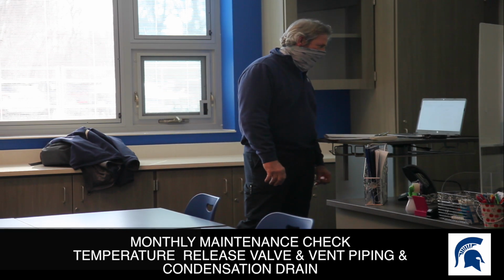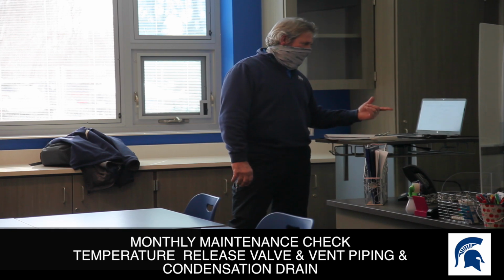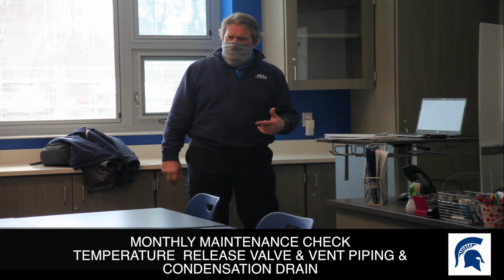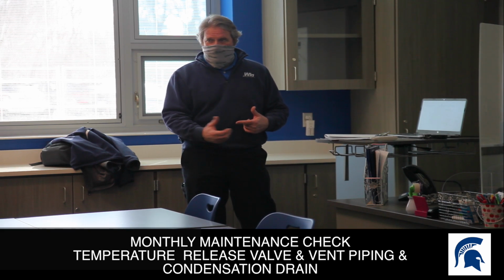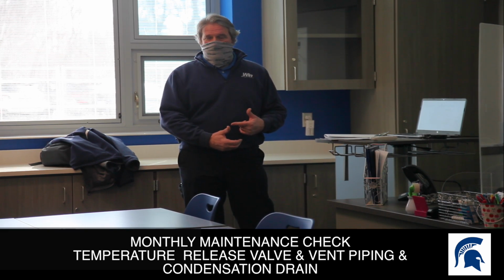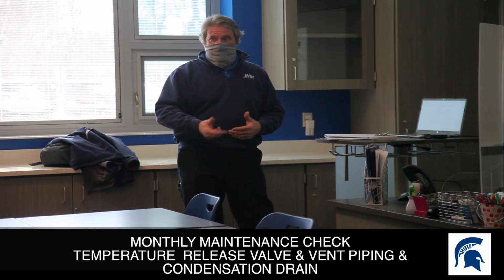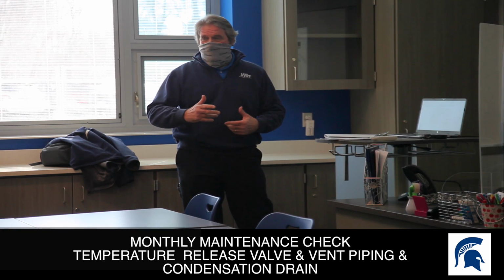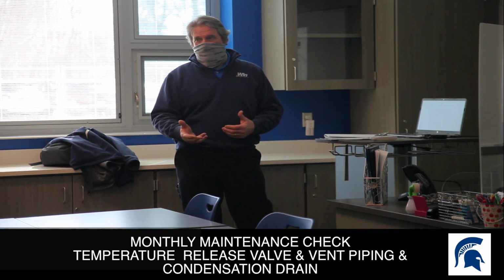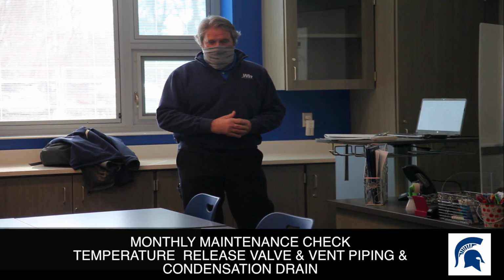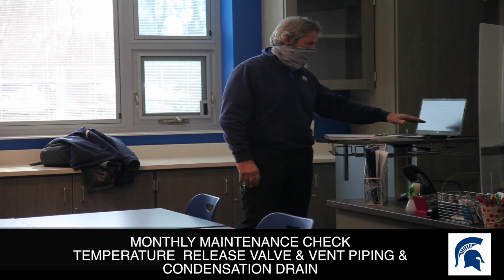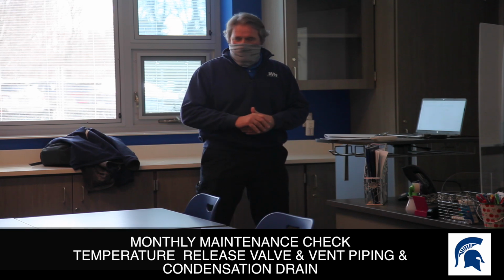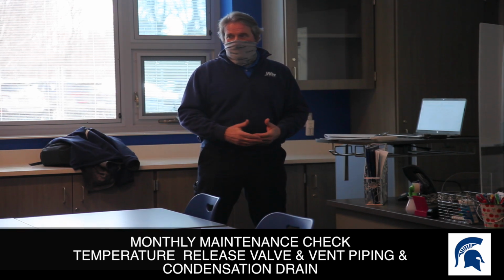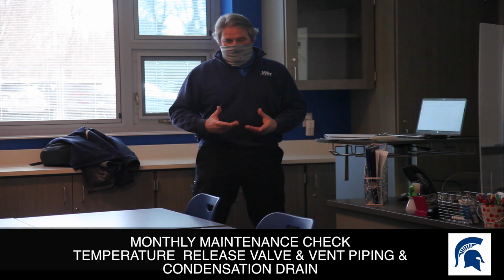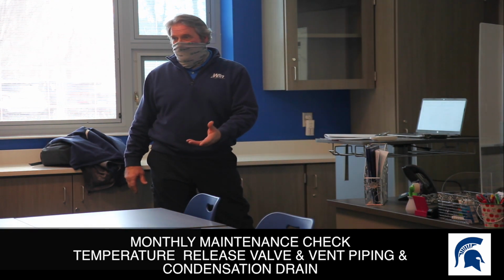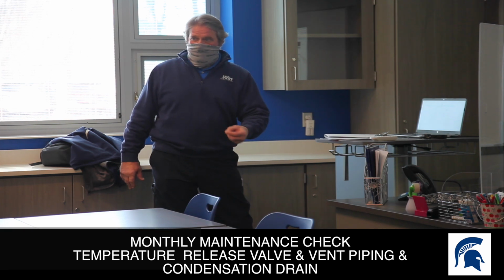And then your condensate drain, you should have the condensate drain there with, I think you have the neutralizing kit on there as well. So you just have to make sure that that's flowing, obviously. How often do you got to change the stones in there then? The media should be changed probably annually. It doesn't really tell you in here. As long as it's functioning and you can see the media in there, then it's doing its job. It's not really going to break down if you want to change it annually. If not, you just keep an eye on it and make sure it's doing this.